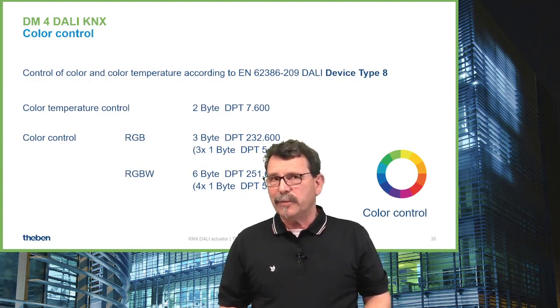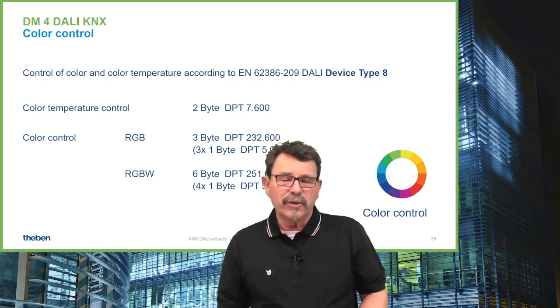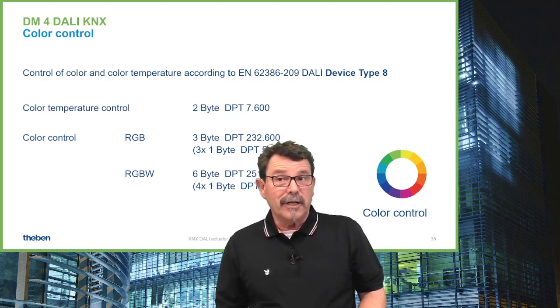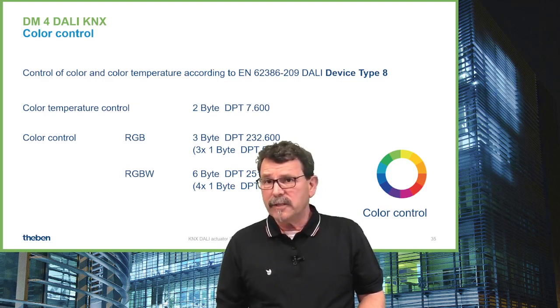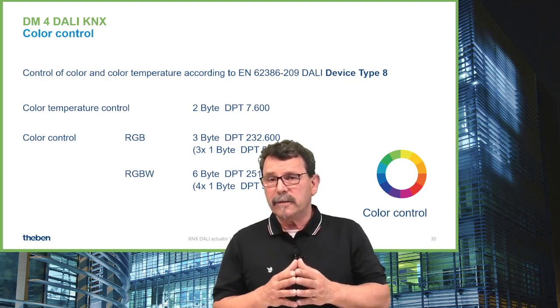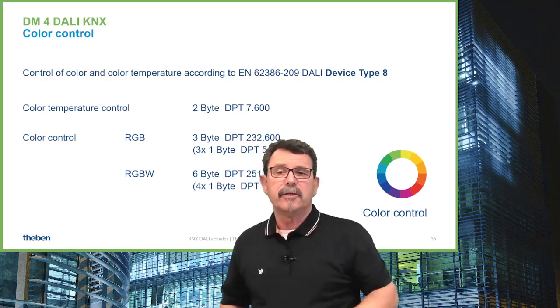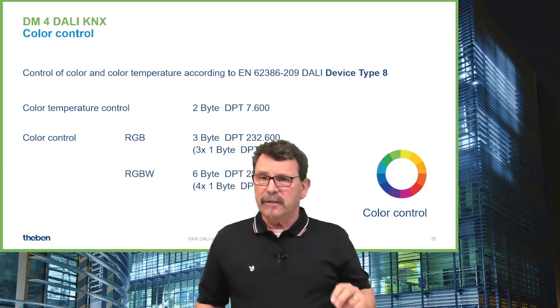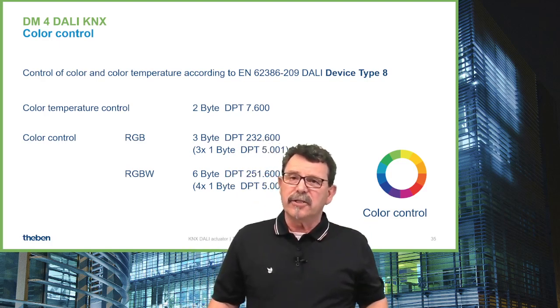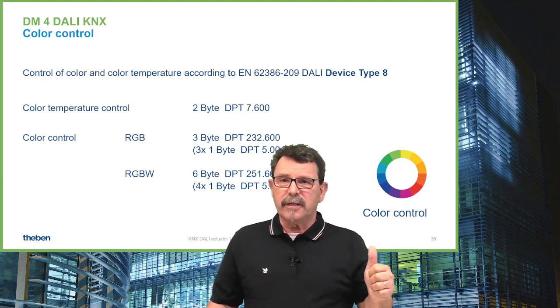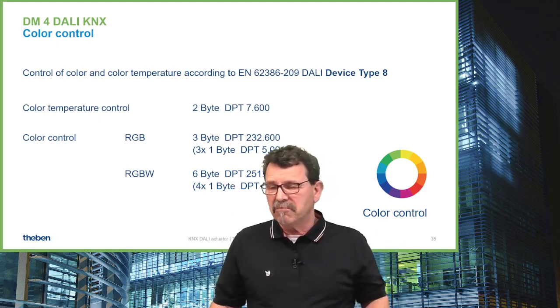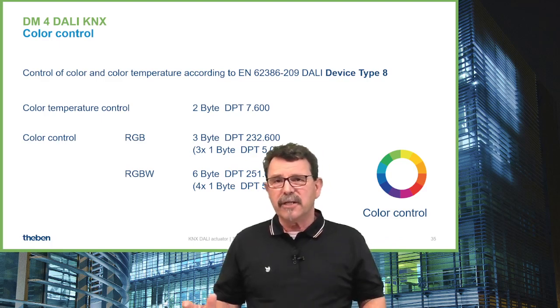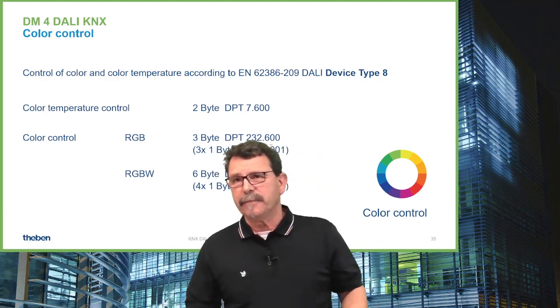With this device type 8, we support temperature control, which is 2 byte, which supports RGB, 3 byte, or RGBW, 6 byte. You can have one control communication object, 6 byte. You can separate the color channels as well - separate red, separate green, separate blue, separate white. Can do as well, your choice. It's a matter of the application settings, however.